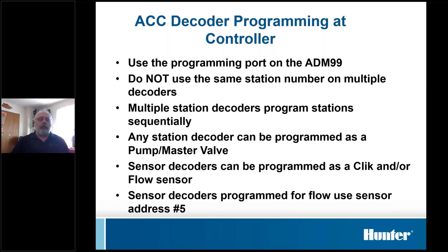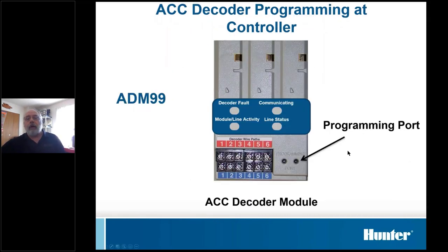And one thing we encourage people, if you're using sensor decoders and you're using a flow sensor on ACC, we always set the address to number 5. You don't have to, but the only thing that can be set to sensor address number 5 is the flow sensor. That way anybody that's working on one knows where to look for it. And it gives you a free sensor port, not that you probably are going to have 4 other sensors hooked up, but you could.